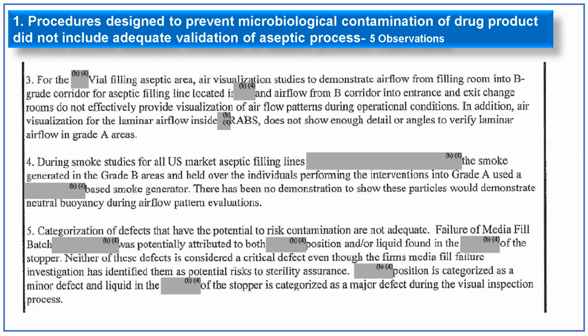The third subpoint under the first 483: for the vial filling lines, the aseptic filling line airflow visualization study does not demonstrate airflow appropriately from the filling room into the grade B corridor, and from the B corridor into the entrance and exit change room. So they do not provide visualization of the airflow pattern during operational conditions. Also, air visualization for the laminar airflow inside the RABS does not show enough details or angles to verify the laminar airflow in the grade A areas.